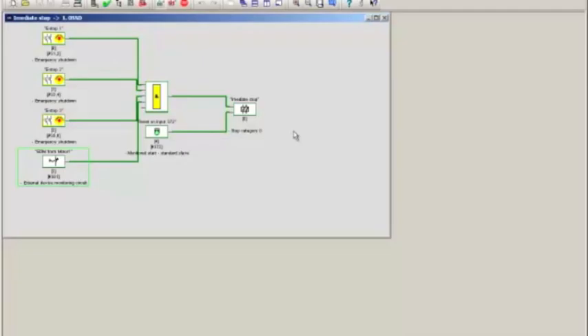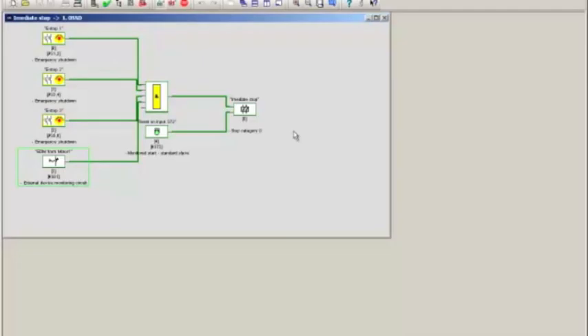If I just shut down my e-stop, then everything will go down. And if I reset my e-stop, then I can provide my reset function to turn everything on. You perhaps saw that for a little bit of time, the EDM connecting line turned red, and that is for that one second time interval that I provided for the feedback circuit to follow the main breaker.